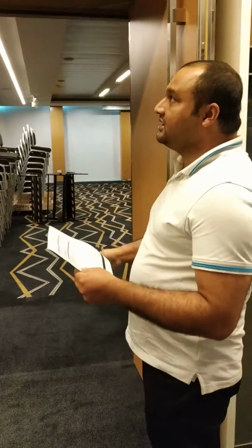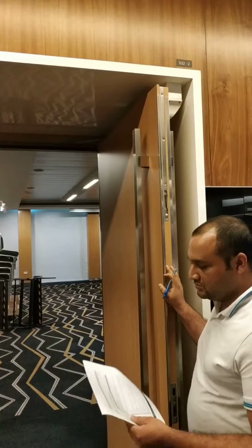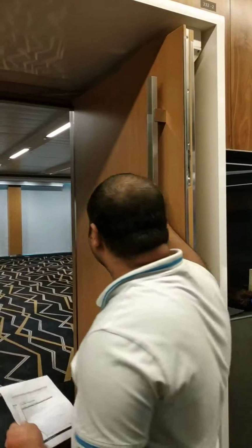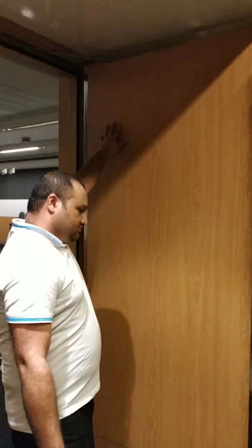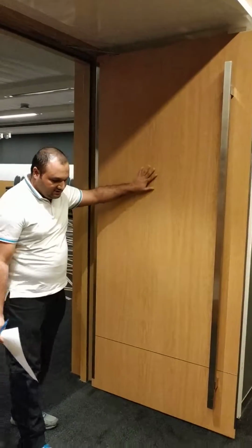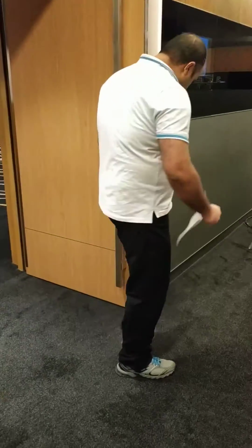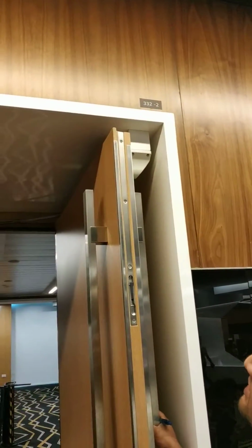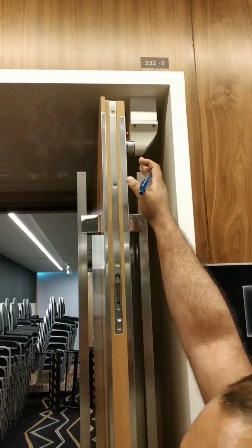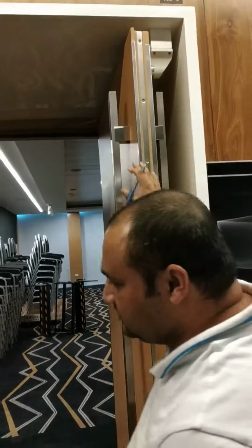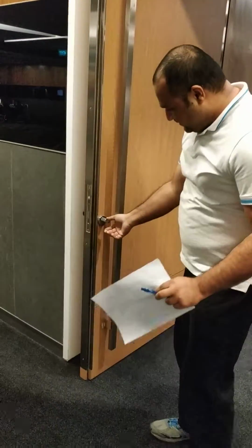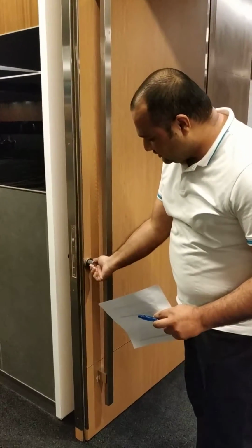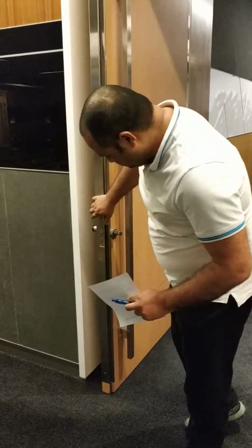Once we ensure no event, we go for the next step. We start from the door checking. We check all the door surface, lamination, any damage of the laminating, any damage of the locking system. We check the functional test of the door, make sure the EM hold is working fine. We also check the door lock system. It's working fine. The functional test: check no abnormality.